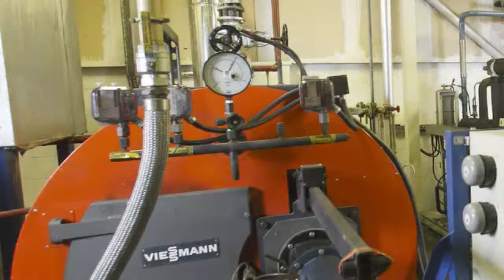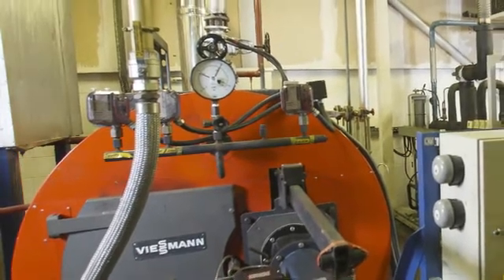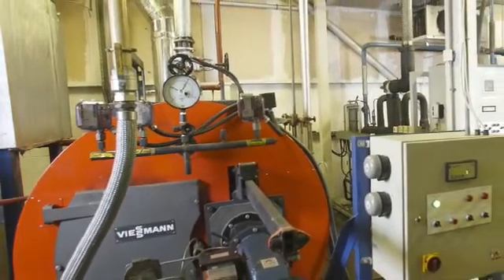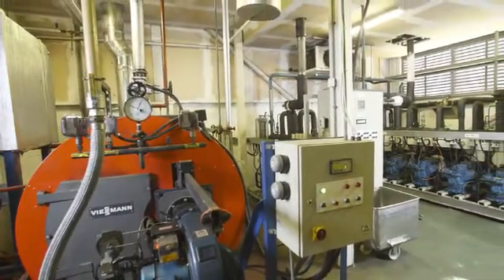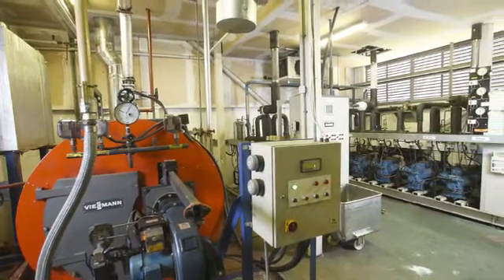The boiler must be regularly serviced and maintained. This is to ensure that it is operating at its optimum efficiency. A boiler service should be undertaken every 6 months. Make sure that the service includes the checking and resetting of combustion efficiency. It is often worth witnessing this. Operating the boiler at optimum efficiency will typically save 3% fuel costs.